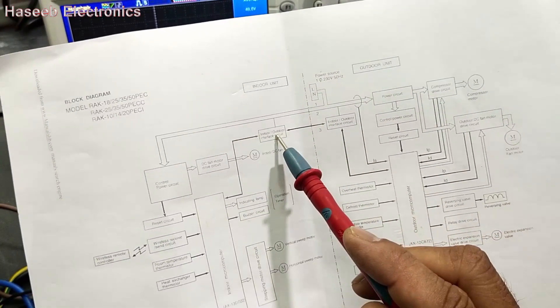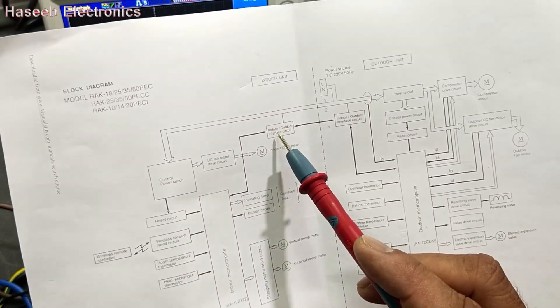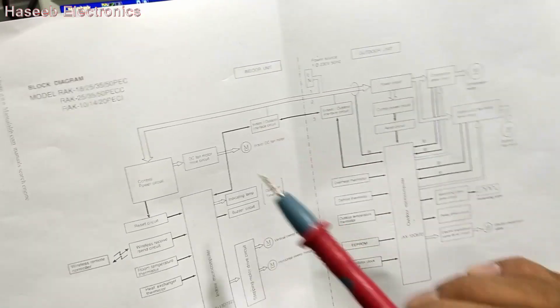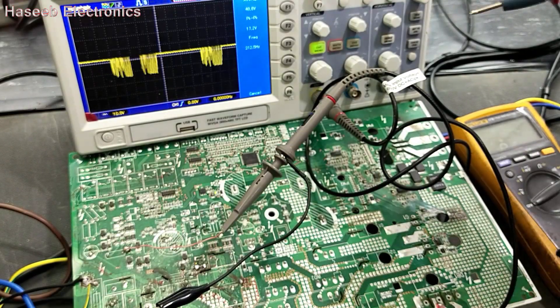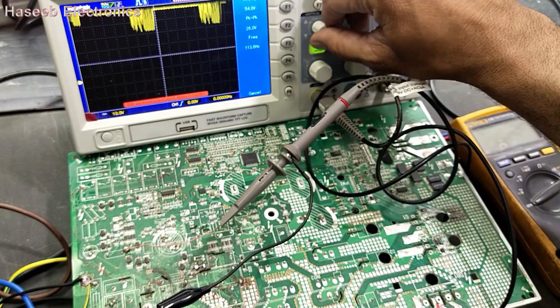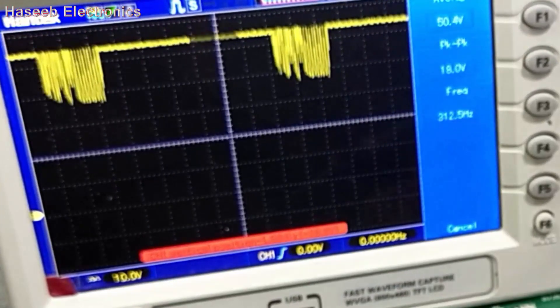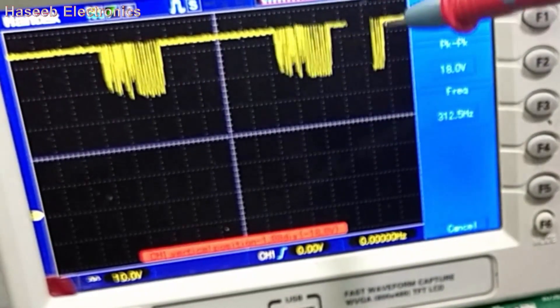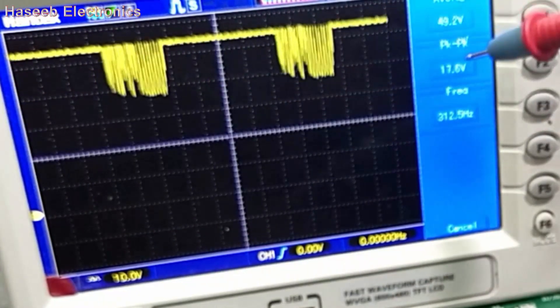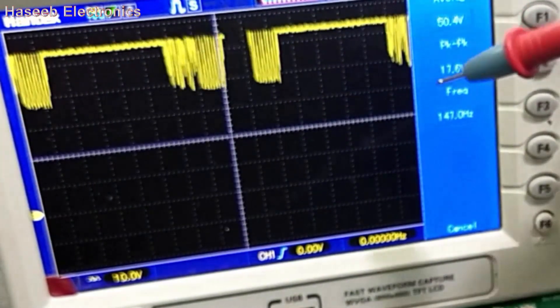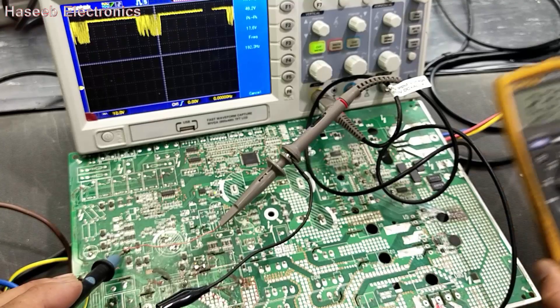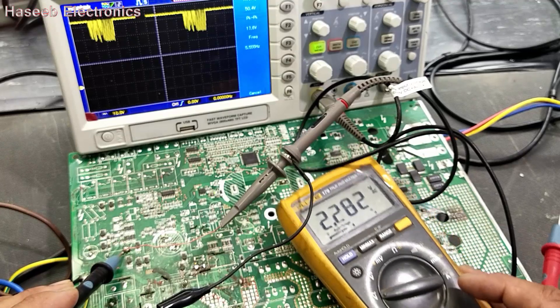In communication, we have a transmitter-receiver interface in both units — indoor and outdoor. It is normally a 50-volt DC level signal, and its switching level is 18 volts. It is an offset DC voltage of 50 volts.